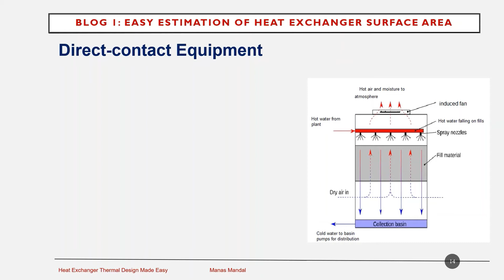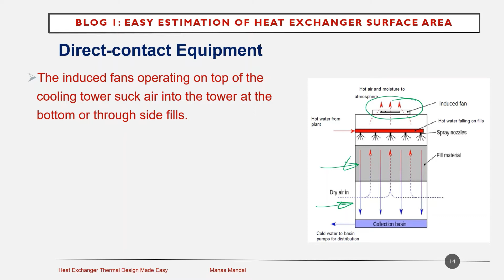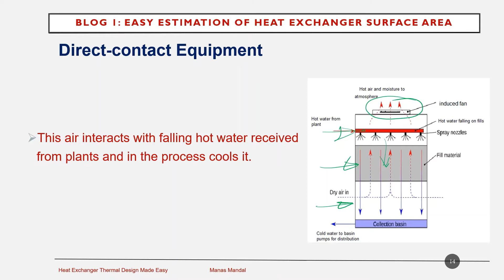In direct contact equipment, we can have a cooling tower. The induced fans in the cooling tower, operating on top of the tower, suck air into the tower at the bottom or through the fills. The air interacts with falling hot water which is coming from the plant, falling on the fills, and in this process the water gets cooled. Heat is transferred through convection and conduction processes, along with some kind of mass transfer, where some amount of water is discharged from the top along with warm air.